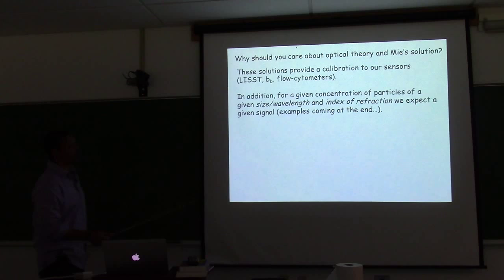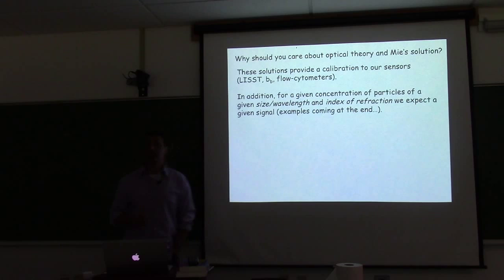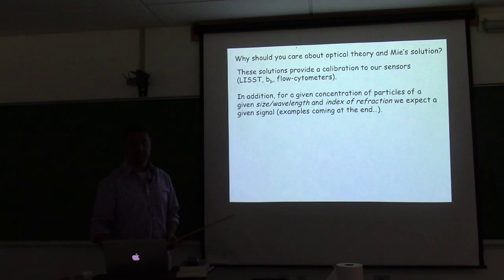In addition, I hope to convince you — through a little exercise we'll do at the end — that for a given concentration of particles of a given size, wavelength of light, and something about the index of refraction, we know something about the signal our instrument should give us. And if it doesn't match, it can help tell us that there's a problem: our calibration is off, or something really weird is happening in those waters.